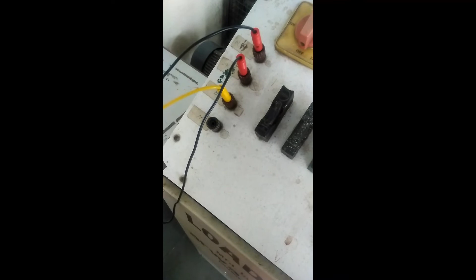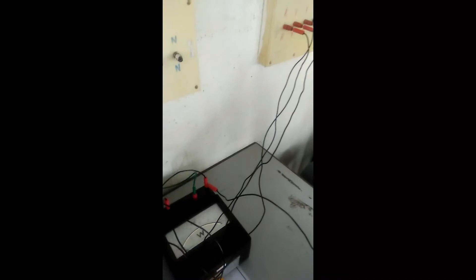Now I have changed the connections. See the connections. Now this Y terminal of the auto transformer is directly connected to load terminal Y, and this B terminal is connected to V of this wattmeter, and this V is connected to the B terminal of this load. Now we will take the reading again for 200 volt. Again increase the supply voltage up to 200 volt. You have to keep the condition the same, that is 200 volt and the same load, and note down the reading for W2.